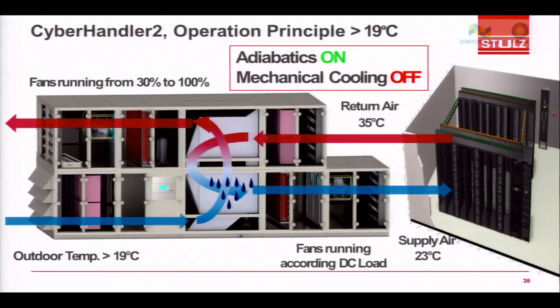Now let's come back. Outdoor is still getting greater than 19 degrees Celsius. We are still achieving cooling with adiabatics on. You still don't have to get the compressor on, only using good quality equipment, good quality fans, and again you don't have to go for standby. Standby can be built in fans, standby can be built in the DX system also. You don't have to go N+1. N+1 can be built in the system itself.